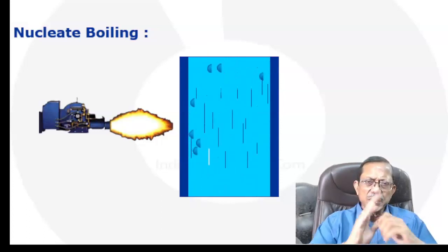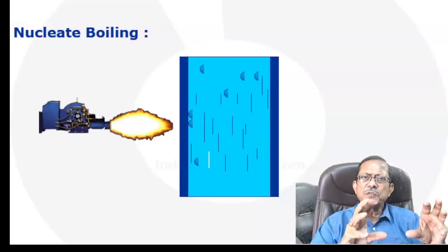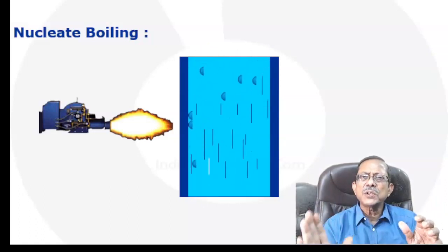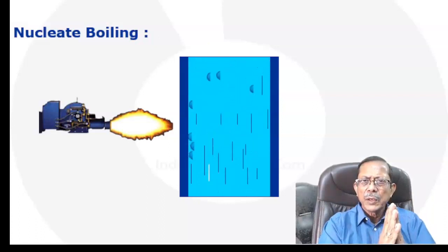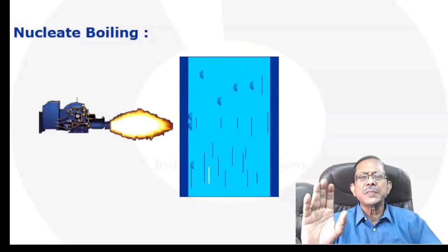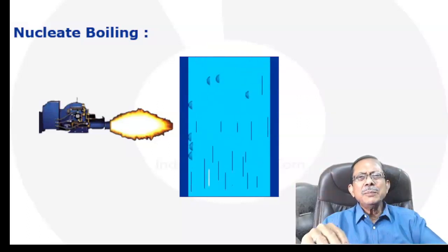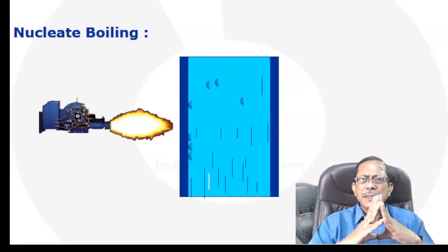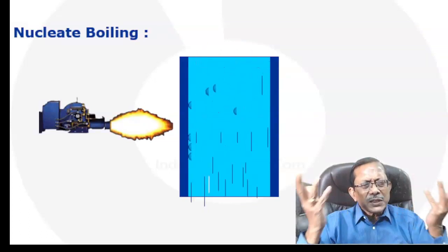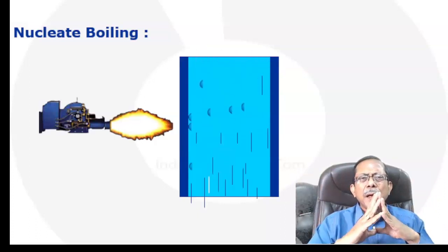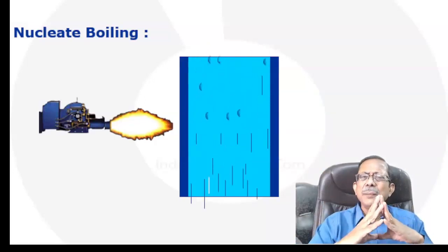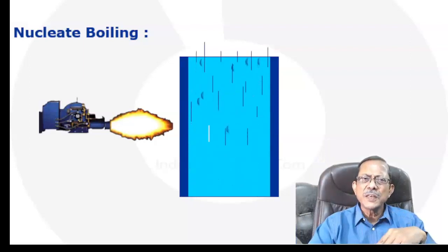So because of this, since the steam is forming at a saturation temperature, immediately leaving the surface, and the water at saturation temperature coming in contact with the metal again, the metal temperature will never exceed the limitation temperature of 370 degrees centigrade. And that's why we can very well use the carbon steel metallurgy in our tube, right? Now a couple of questions might come to the mind, right? For example, steam bubbles are forming. Why is it getting dislodged immediately? What makes it move away from the surface, right?